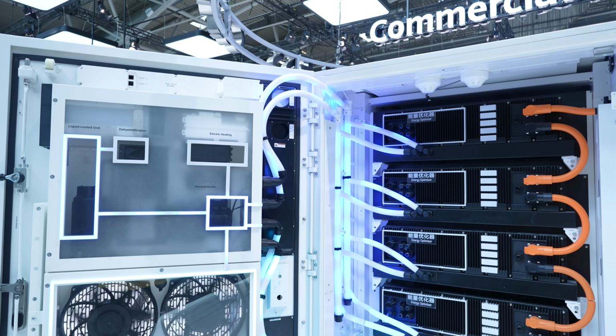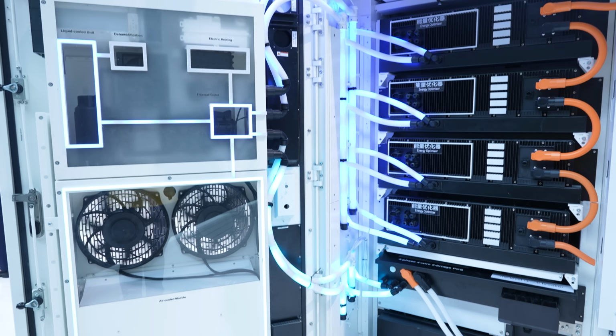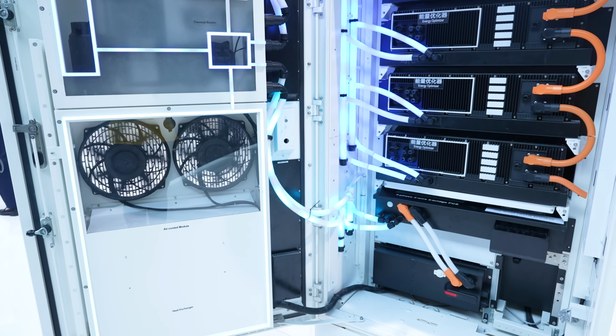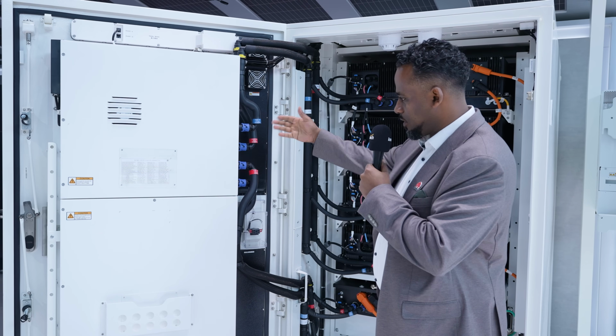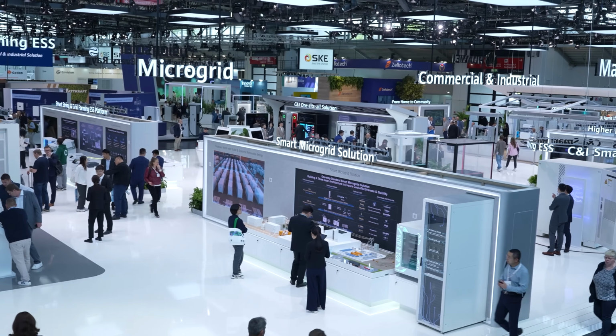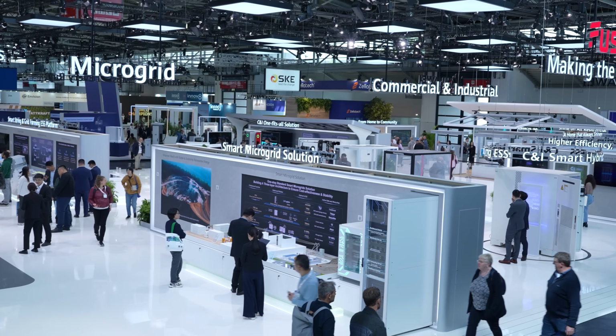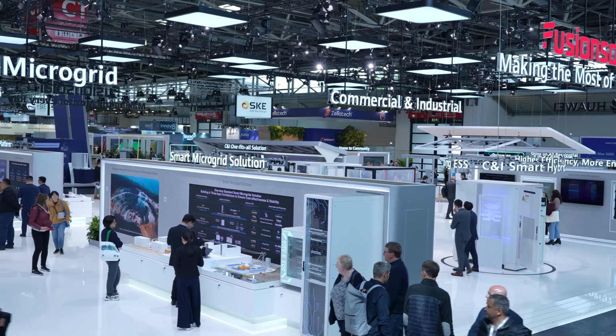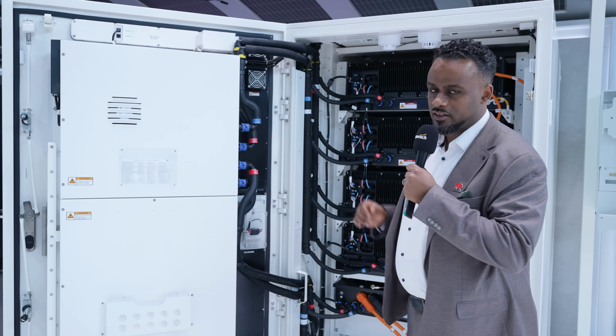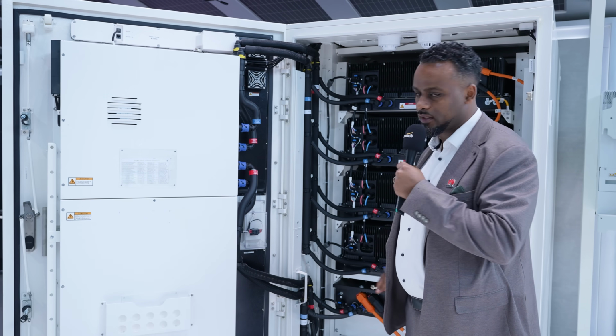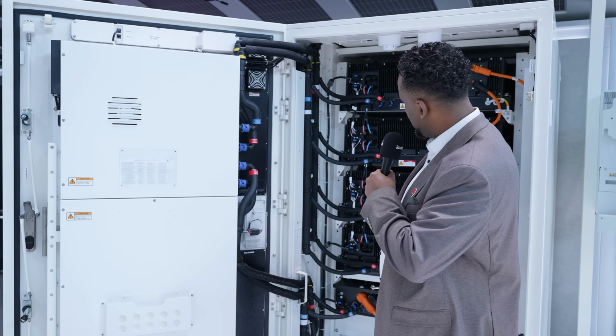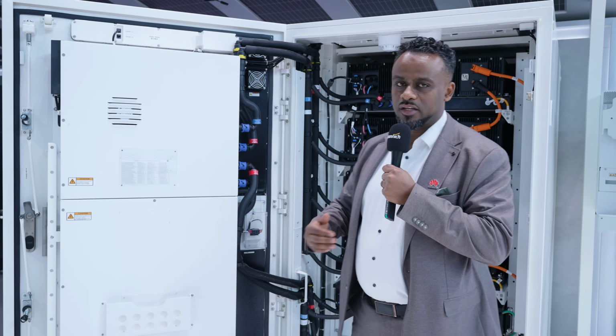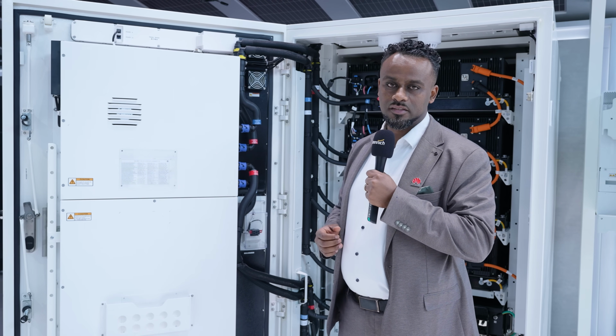For moderate temperatures, we only use air cooling, on the bottom side of the cabinet, to cool the heat exchangers, and then cool the battery packs as well as the PCS. Worth mentioning, in low, negative temperatures, we can use the heat dissipated by the PCS to heat up the battery packs, and based on that reduce consumption from the electricity grid and achieve the highest round-trip efficiency on the market.